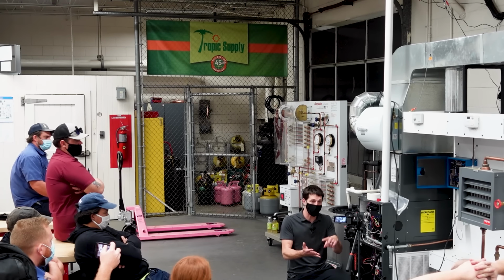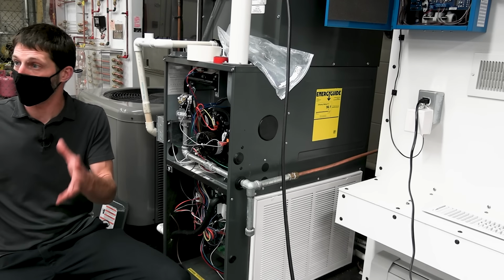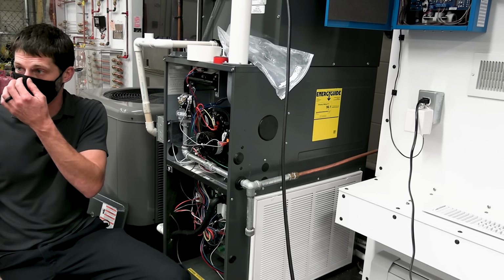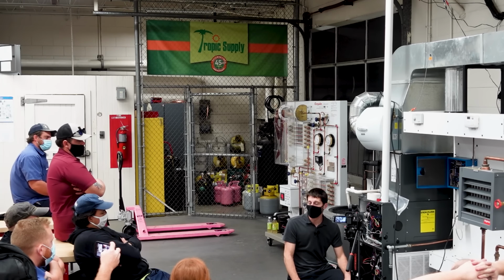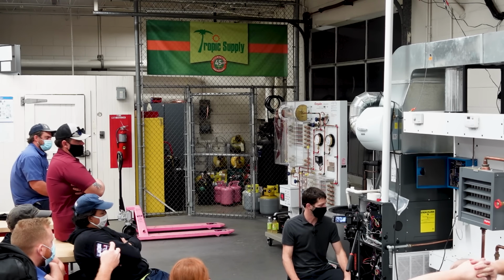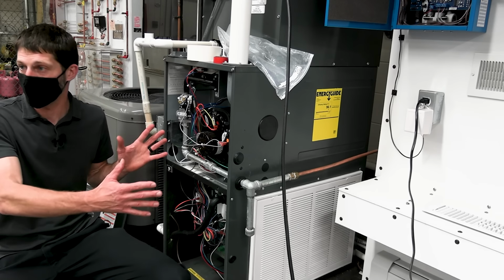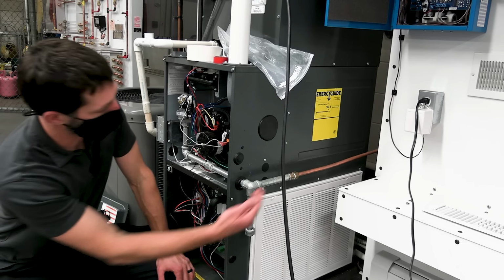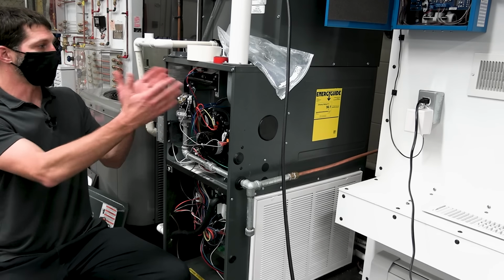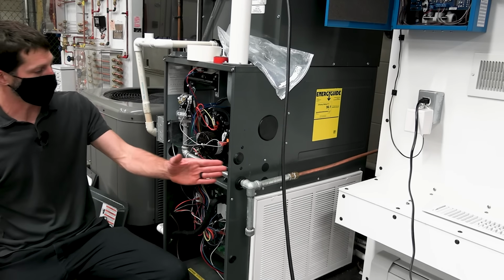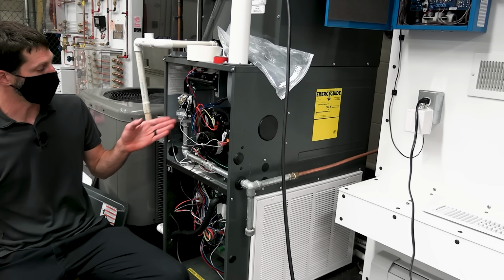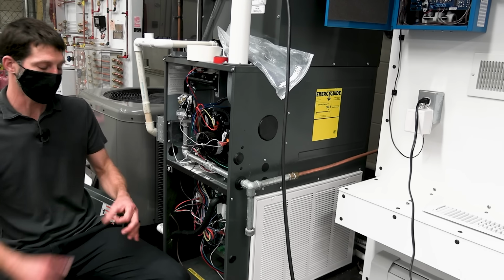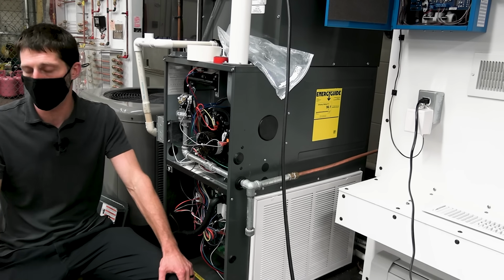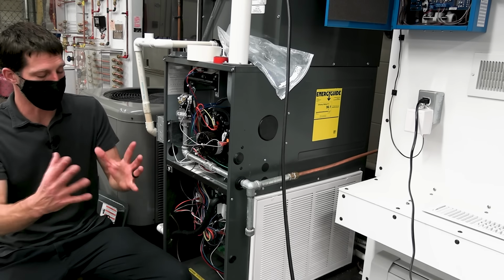All of the gas line stuff and the combustion air stuff that he's talking about is all in that International Fuel Gas Code book, and the newest update will be 2021, but we're still using the 2018 version. So that's for all your sizing of the gas lines. You're going to size your gas line for the amount of BTUs of the furnace, and you're going to have to reduce down once you get to the furnace, because you normally have 1/2 inch coming in. Larger package units will have 3/4 or even 1 inch, depending on the BTU size.